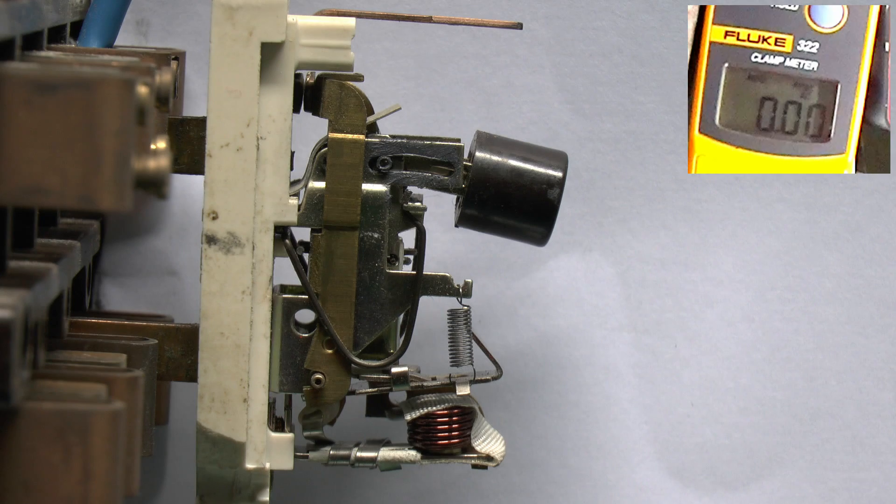Now this is a side view of the circuit breaker. And we've got the power coming in at the back in the usual fashion. And you can see at the bottom there, I've got that strip with a little magnetic coil on the end of it, and that should be the thing which should bend when power is applied. Now this is a 5A circuit breaker. So that means that if you applied 5A there, it should have no problem in holding that indefinitely. So we'll turn it up to 5 and then obviously increase the current above that and see if the strip bends or not.